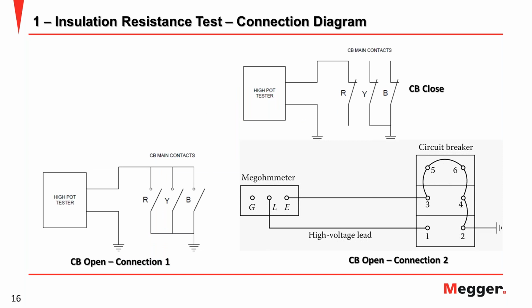And this is the connection diagram. For the connection diagram, you can also see this connection in some standards, but we do it in two ways: when the breaker is open, and when the breaker is closed. When the breaker is closed, normally you test like this: you inject voltage to one pole, one phase, and the other two phases you short to the ground, and then you do the same on the other phases.